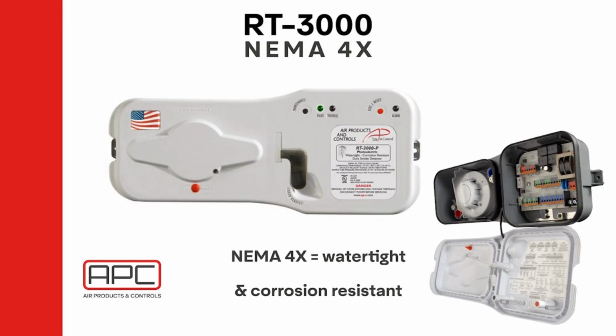As with the SL2000 detector, the wiring instructions are affixed to the inside, but they are fixed so that when the cover is hanging from the tether, the instructions are right side up for the contractor to reference. Dedicated terminal blocks allow for easy wiring. The detector is also universal voltage with the higher voltage range. The detector can be mounted horizontally or vertically, and the sampling tubes are staggered to allow for drainage for any condensation buildup that may occur.